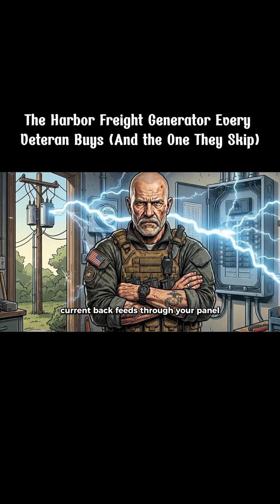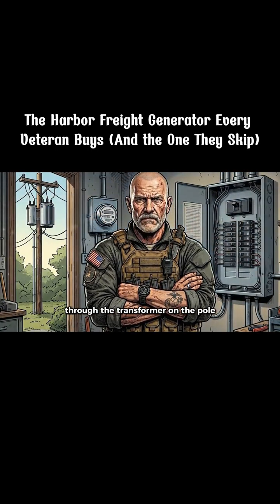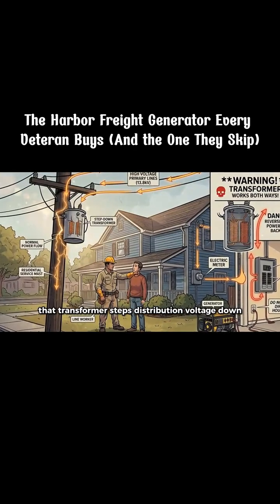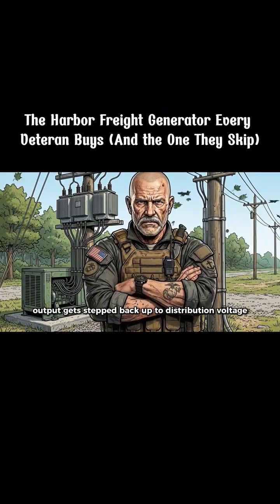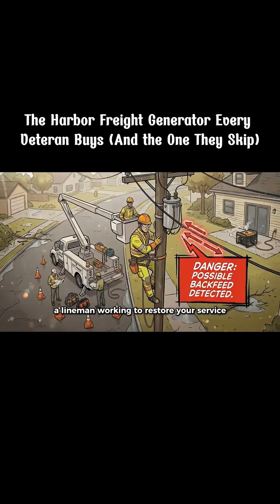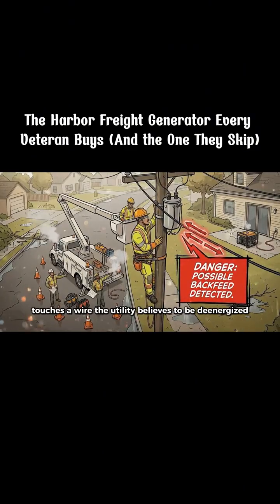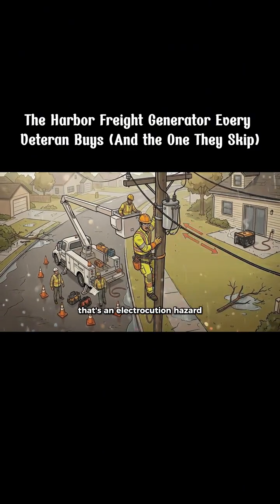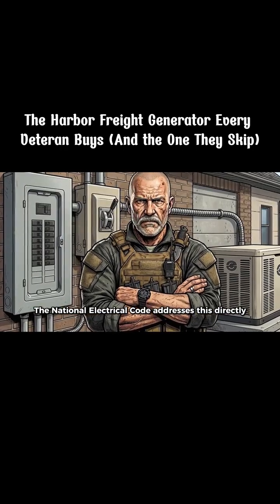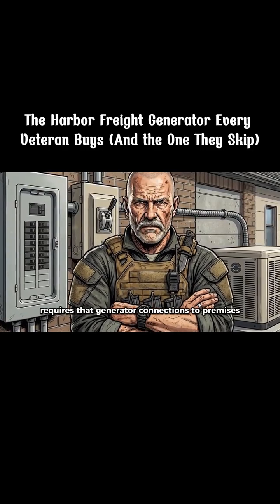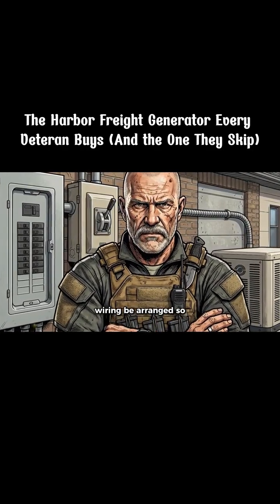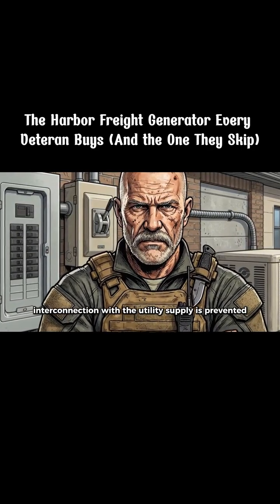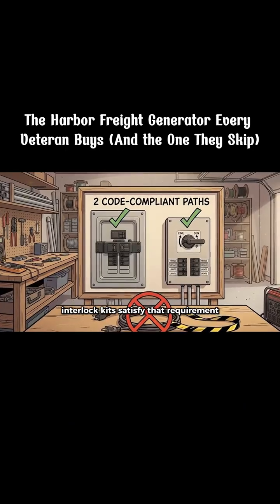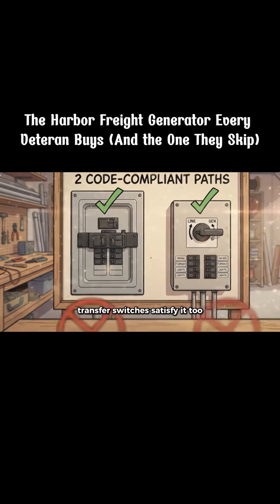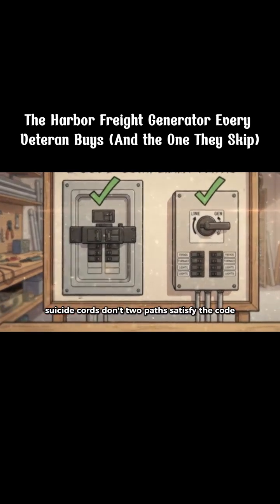When the utility power comes back on and your main breaker is still up, current backfeeds through your panel, up through the meter, through the transformer on the pole. That transformer steps distribution voltage down for your house. It works in reverse too. Your generator's output gets stepped back up to distribution voltage on the pole side. A lineman working to restore your service touches a wire the utility believes to be de-energized. That's an electrocution hazard. The National Electrical Code addresses this directly. Article 702 requires that generator connections to premises wiring be arranged so inadvertent interconnection with the utility supply is prevented. Interlock kits satisfy that requirement. Transfer switches satisfy it too. Suicide cords don't.